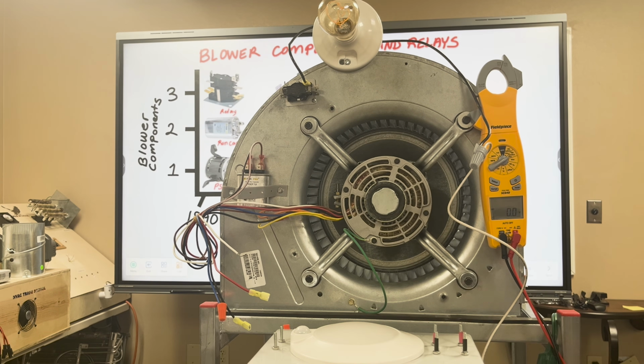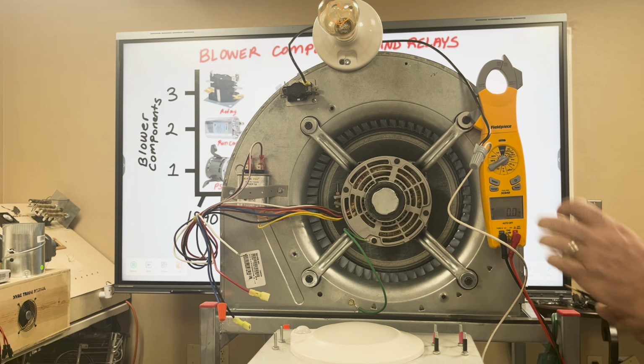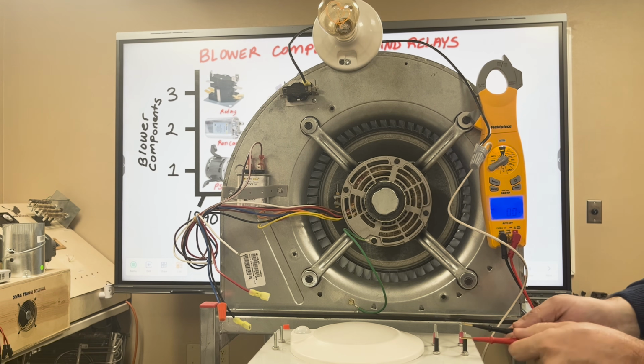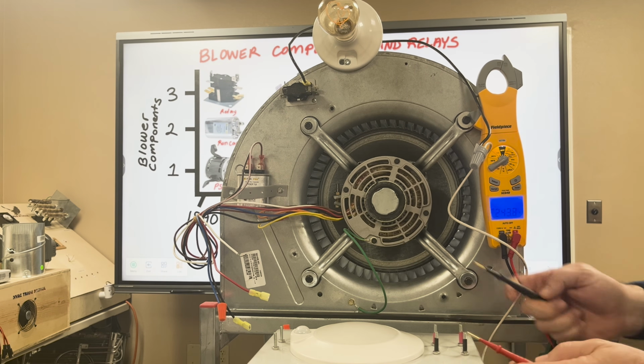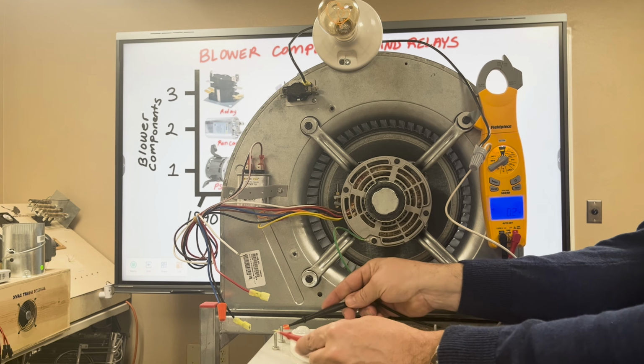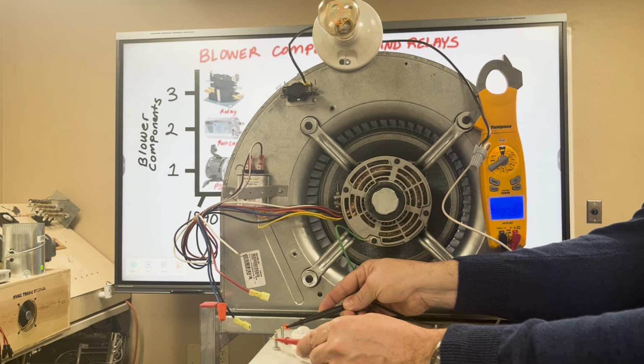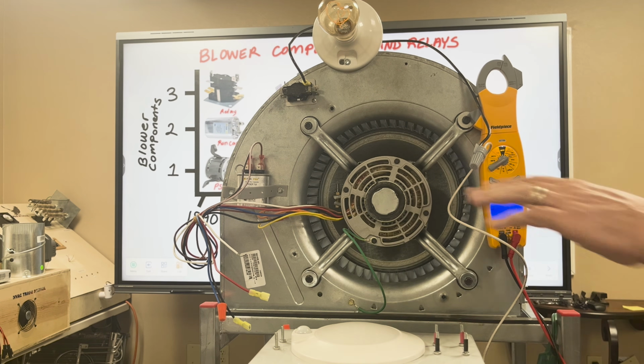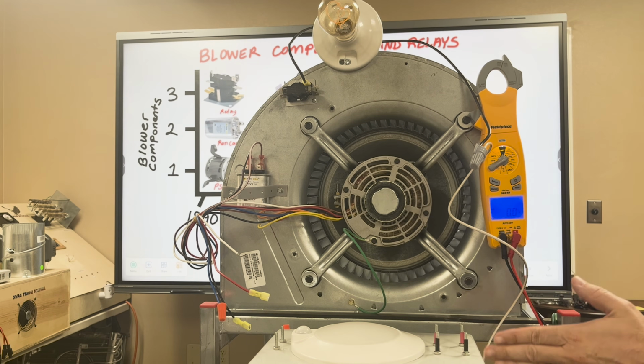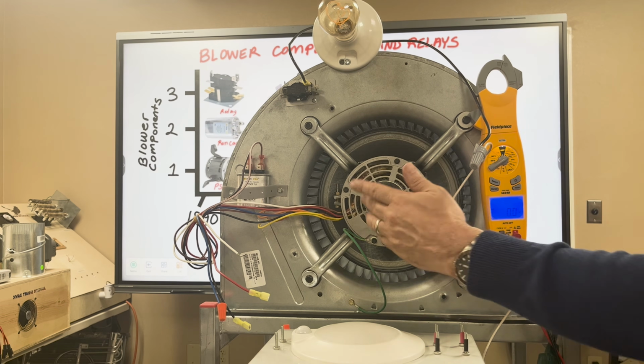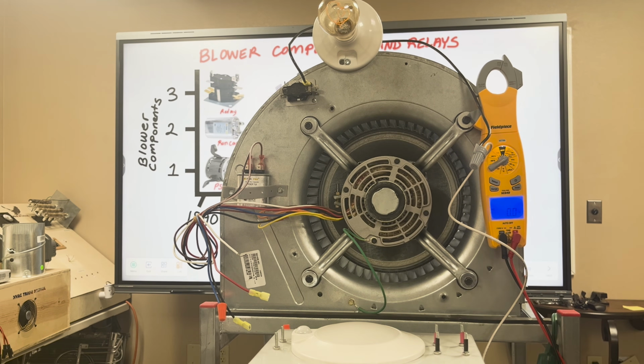I've got a power supply now. We got it a little bit in frame, so you can see here between L1 and L2 I have 243 volts, and I have 24 volts down here as well, 27.5 volts. So we have live power. I'm going to wire 24 volts to the relay. I'm going to take both legs of power and energize this motor. This PSC motor is going to require both legs, L1 and L2, for it to run.